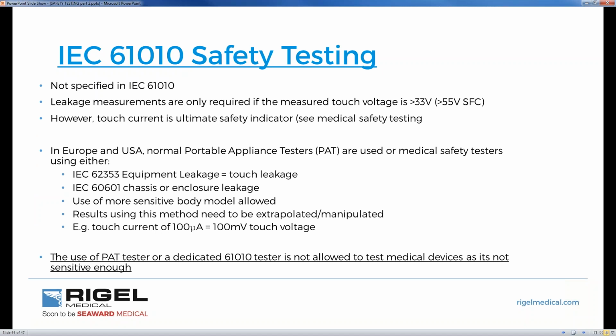So electrical safety is not really typically specified in 61010. Leakage measurements are only required if measured touch voltage is greater than 33 volts. However, touch current is ultimately a safety indicator. Over in the UK, and in Europe, and possibly parts of the US and Australia, we would use portable appliance testing to measure 61010. But with the Rigel device, the 288, you can measure 61010 and test laboratory equipment just by extrapolating or manipulating the figures. So we can use touch leakage.